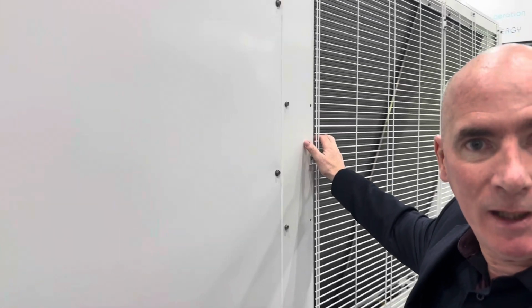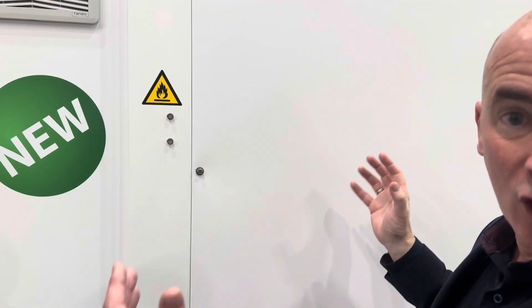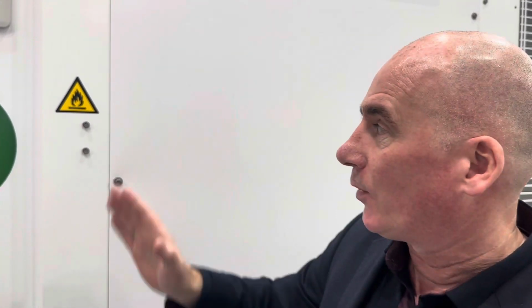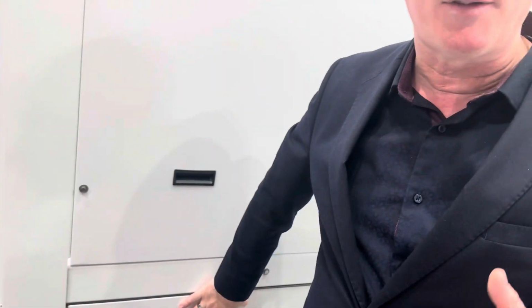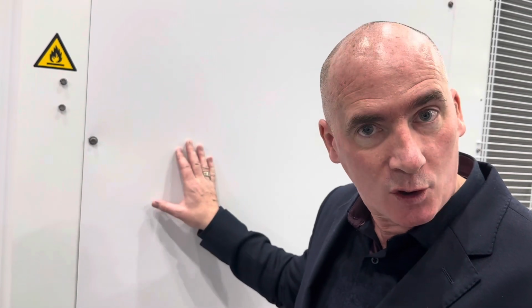The fin spacing, by the way, is 2 millimeters, which is very important because obviously it helps minimise blockages. They also come with protection grills, very important because, again, propane is highly flammable, so there are elements of safety that historically you wouldn't have necessarily had. The electrical panel is in a completely separate compartment, whereas before it could have been somewhat connected to your compressor housing. In the compressor housing, we have electronic leak detectors, and there's actually a little fan. By the way, the fan is the only ATEX rated component. You don't need to have all your motors ATEX rated, even though it's propane, so just so people are aware of that. However, in the compressor housing, the fan is ATEX rated, and that's just to circulate. If there's a refrigerant leakage, it'll circulate, and it makes it easier for the leak sensor to pick it up.